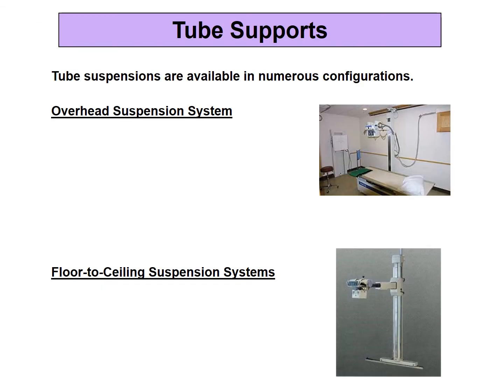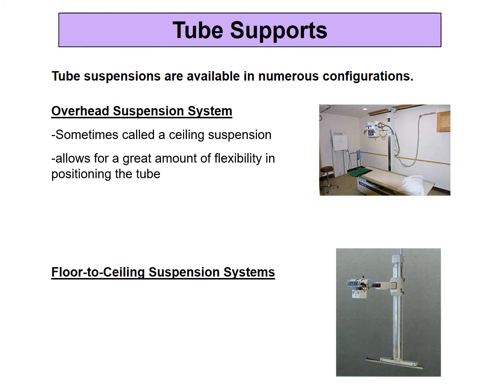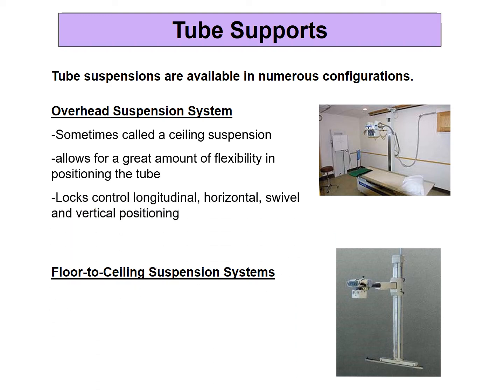There are different types of tube supports. We've got the overhead suspension system, which is what is used in most hospital settings. It's sometimes called a ceiling suspension system. It's a good type of system to work with because it allows for a lot of flexibility in positioning the tube. And it has locks that control longitudinal, horizontal, swivel, and vertical positioning. And of course, there are detents or centering locks that lock the tube into place.